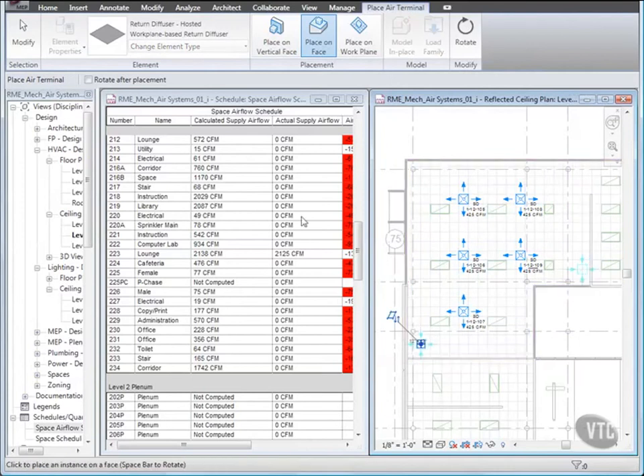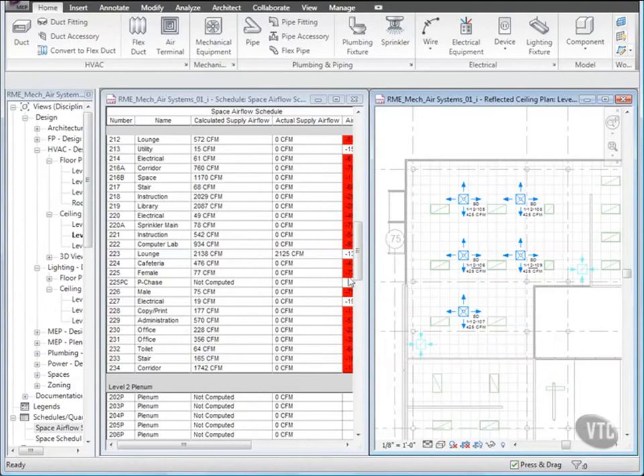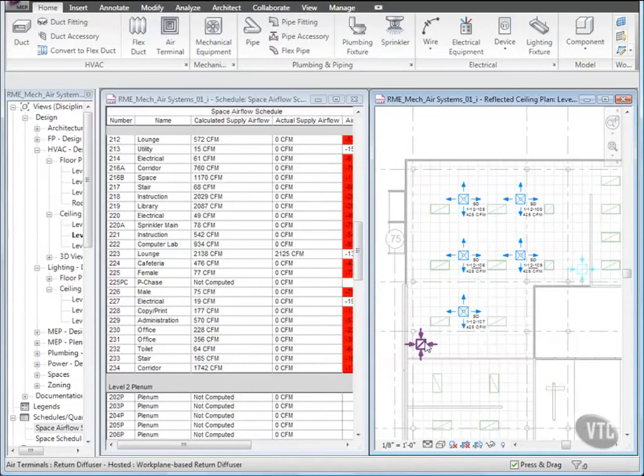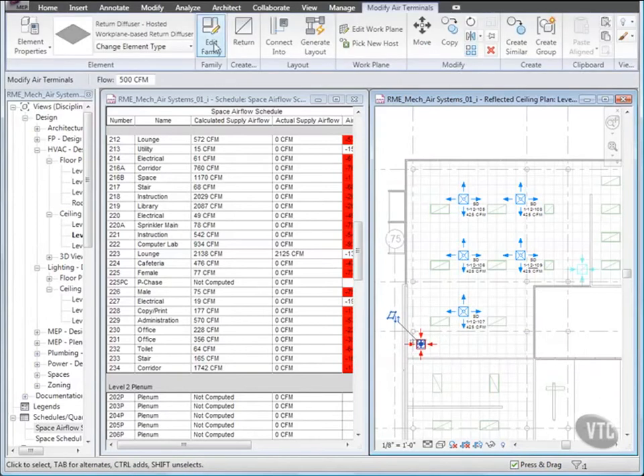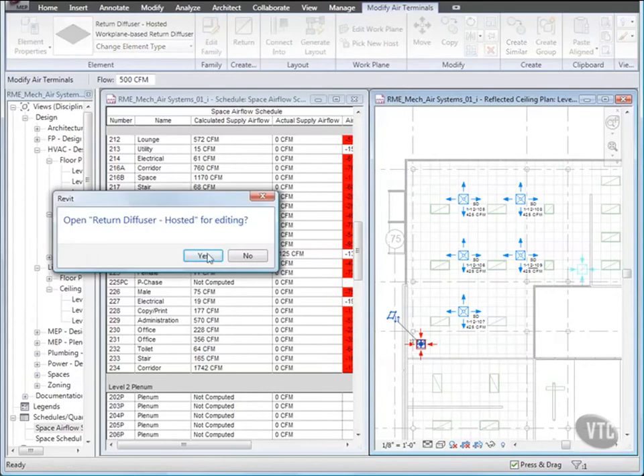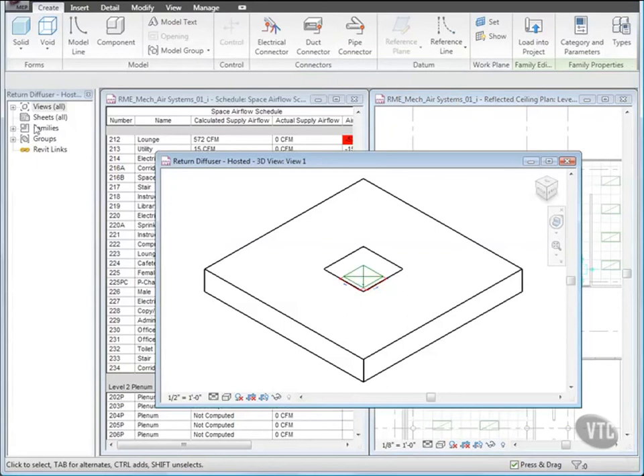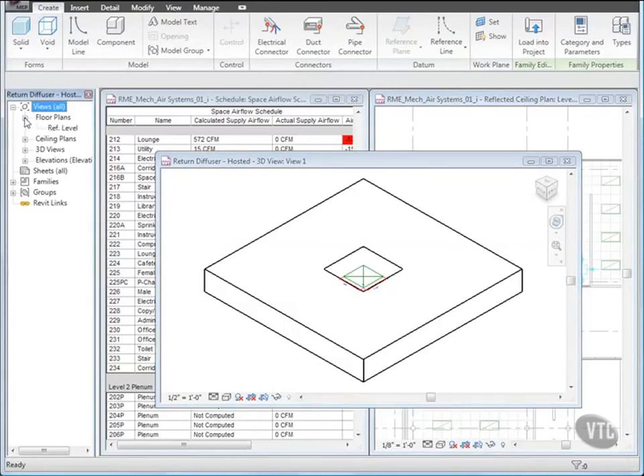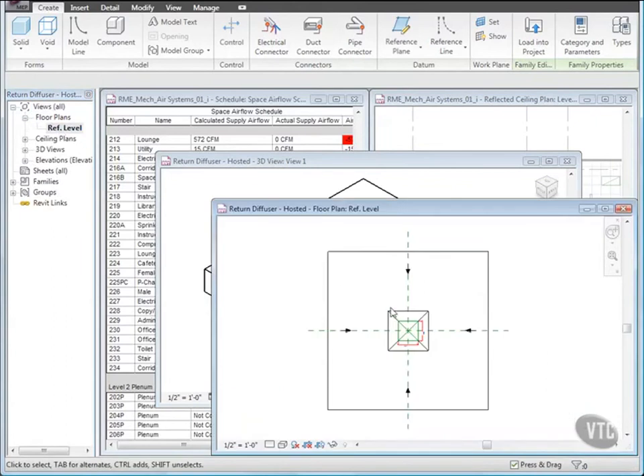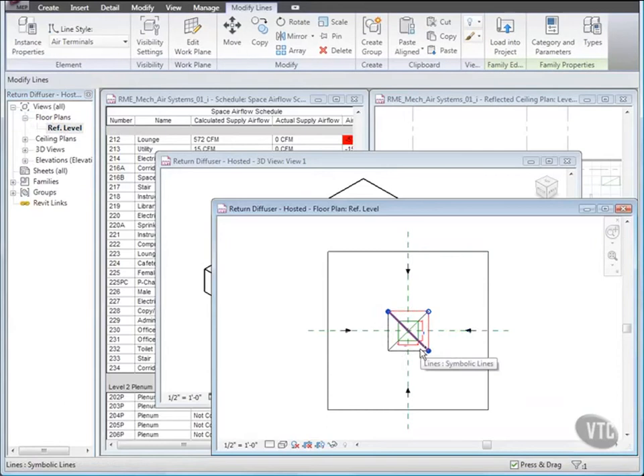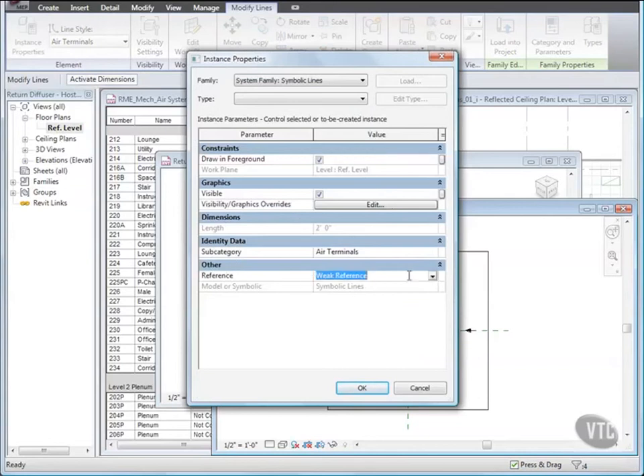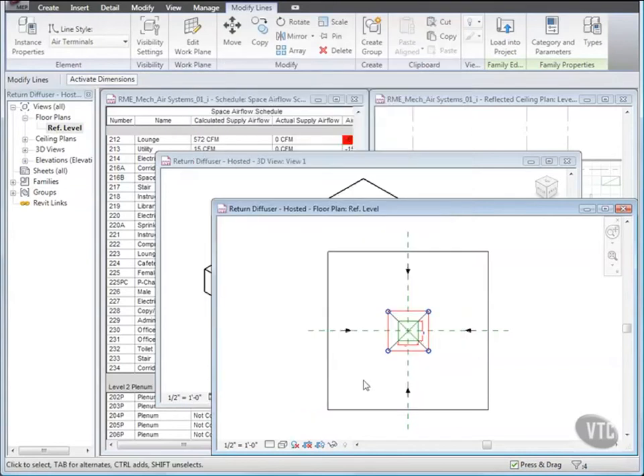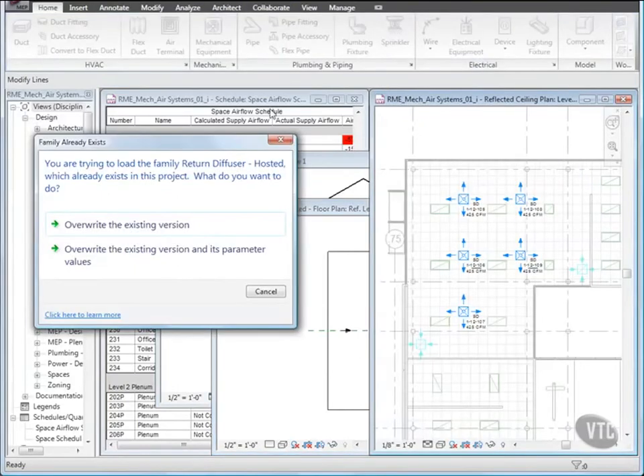Then click Modify. We now need to edit the Diffuser family in order to align the edges to the ceiling gridlines. Select one of the Return Diffusers, and from the Family panel, click Edit Family. In the Revit dialog, click Yes. And in the Project Browser, expand Views, Floor Plans, and double-click Ref Level. Select the symbolic lines shown using the Ctrl key. Then click Instance Properties, and for Reference, select Strong Reference, and click OK. Then click Load Into Project. And in the Family Already Exists dialog, click Overwrite the existing version and its parameter values.